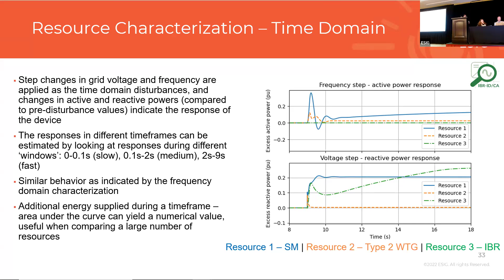Now what's interesting here is type 2 wind cannot provide reactive power support to the network because it's a resource that's going to consume reactive power from the network, since it doesn't have that source in it, which is observable in the plots. If you put a step down reduction in voltage, a type 2 wind will not be able to provide support to the network. And this characterization is something we want to get when we are getting our large system resource characterization.